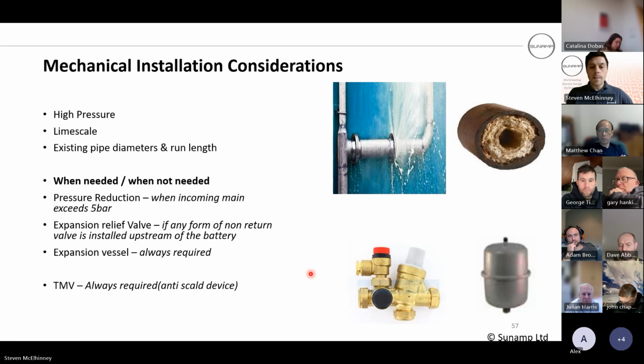So we get a lot of questions about the expansion relief. That's just a flow group manifold. You can just terminate that into a waste pipe. It's not like G3, where you've got to have a tun dish and upgrade to a bigger size pipe, run it to outside and terminate it surrounded by a cage or anything like that. And it's not like a boiler PRV where you've got to run it independently to outside and turn it back to the wall. It's just water pressure. It's not temperature related. So you could essentially just run that into a waste pipe in a customer's house.